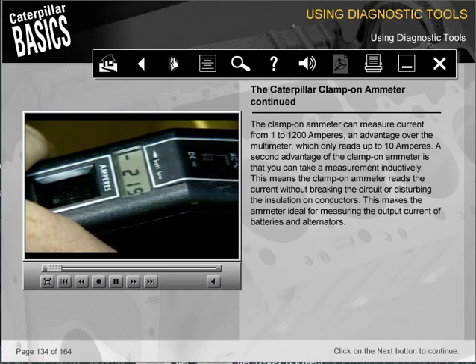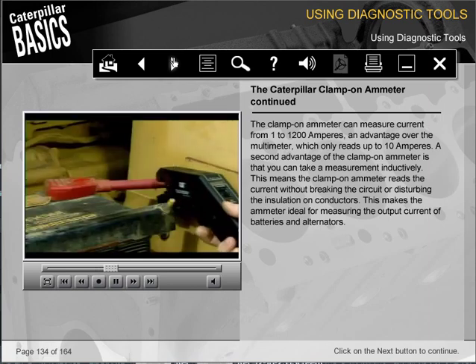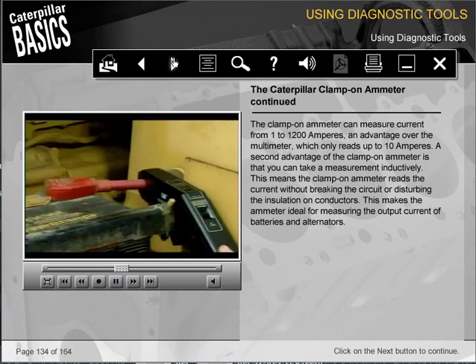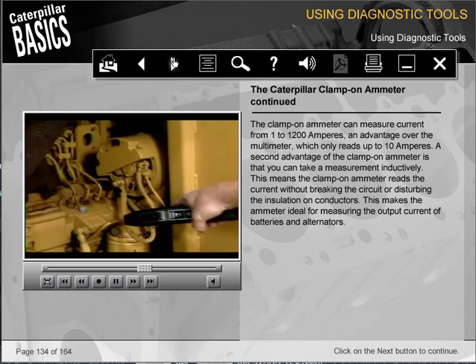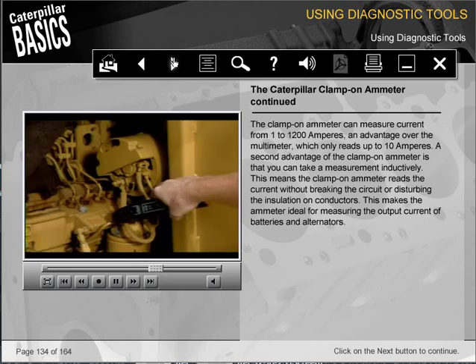The clamp-on ammeter can measure current from 1 to 1200 amperes, an advantage over the multimeter, which only reads up to 10 amperes. A second advantage of the clamp-on ammeter is that you can take a measurement inductively. This means the clamp-on ammeter reads the current without breaking the circuit or disturbing the insulation on conductors. This makes the ammeter ideal for measuring the output current of batteries and alternators.